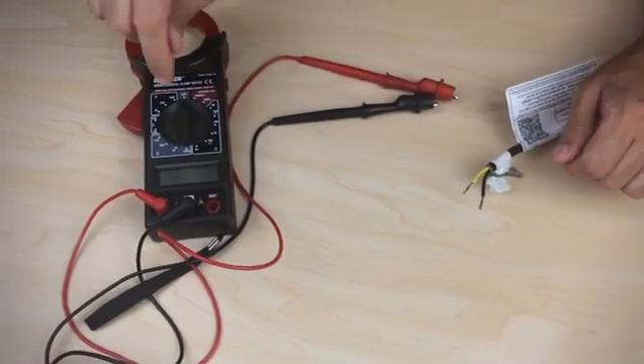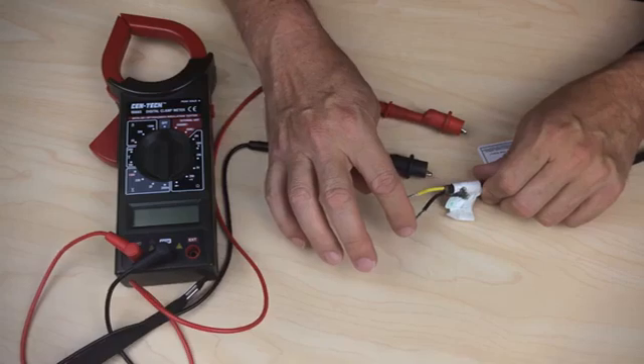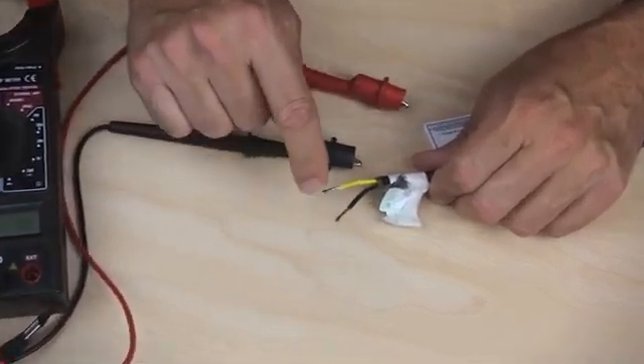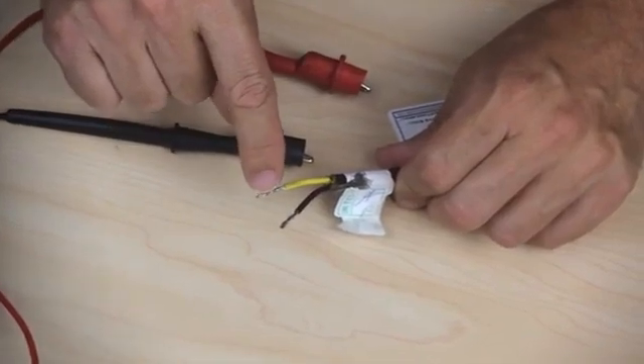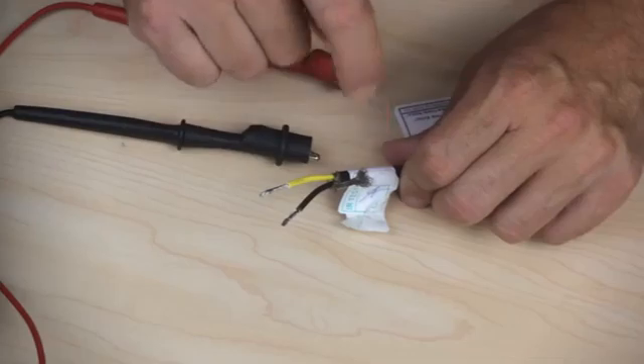To do this, all you're going to need is a digital ohmmeter. On this digital ohmmeter, we want to see if we're getting ohms across these two resistance wires and if we're getting resistance between the resistance wire and the ground or the other resistance wire and the ground.